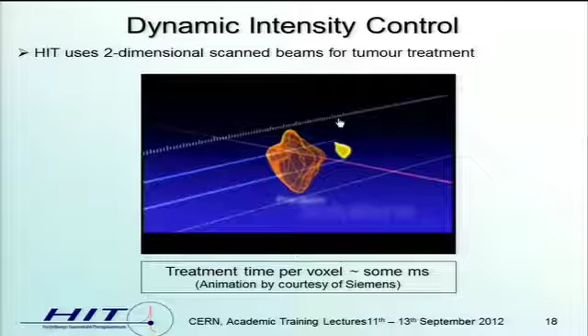Okay, another thing we can do is to adapt our scan beam and the mechanism for that with so-called dynamic intensity control. Here you see the animation which Siemens did for advertisement some years ago. You see these slices of a tumor, and then you see the painting, the scanning, the overlapping of the voxels, which is done there. But the film is not really good, because it shows more or less that there is a linear behavior of the speed of the voxel filling, which is not the case. So we will see that. But keep in mind, treatment time per voxel is in the order of some milliseconds. So keep that in mind. We come back to that in a minute.